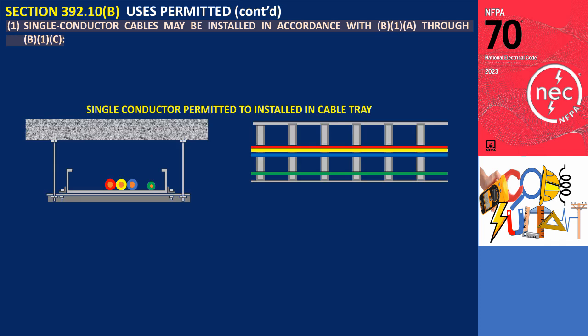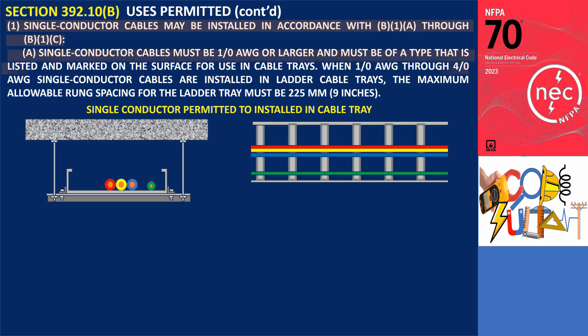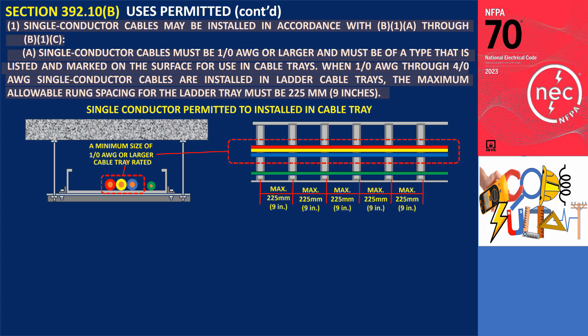Section 392.10(B)(1) covers single conductor cables. Single conductor cables must be 1/0 AWG or larger and must be of a type that is listed and marked on the surface for use in cable trays. When 1/0 AWG through 4/0 AWG single conductor cables are installed in ladder cable trays, the maximum allowable rung spacing for the ladder tray must be 225 mm. This requirement is designed to provide adequate support and stability for the cables, preventing sagging and potential damage.